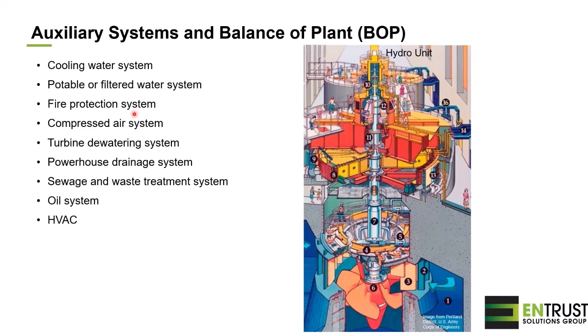We will find also in a powerhouse a fire protection system, and a compressor system that will be required for braking the generator. Sometimes we will find under the generator rotor a set of brake pads that will lift the whole assembly to make sure to brake it. The turbine dewatering system is important because otherwise the runner will remain in water all the time, but we have to do some maintenance there from time to time. So we will close the gates at the upstream and downstream and use a pump to drive out the water.